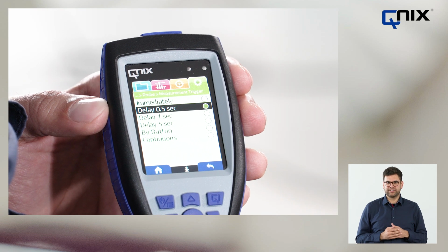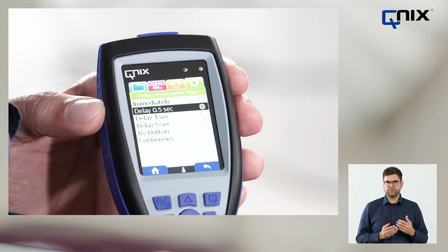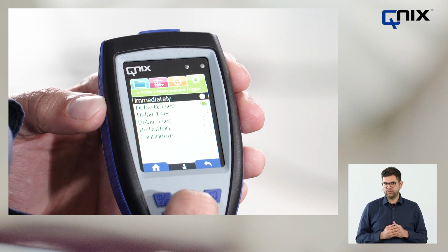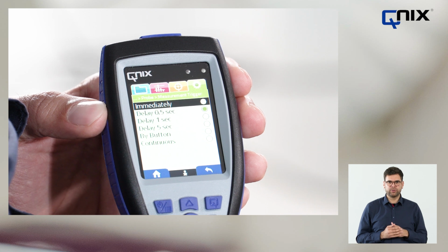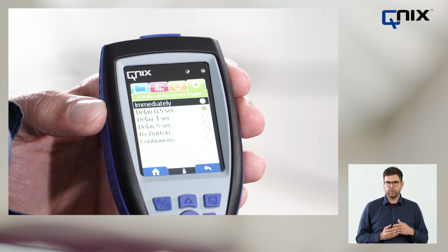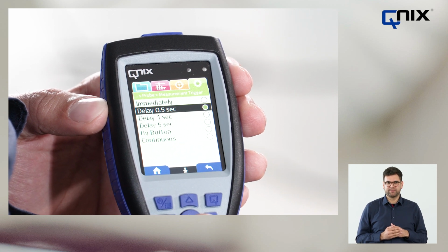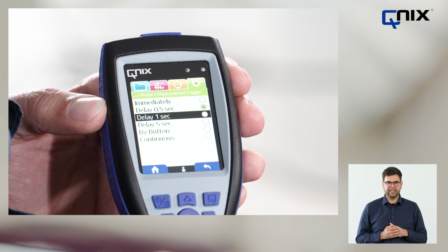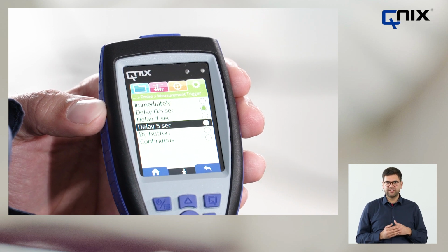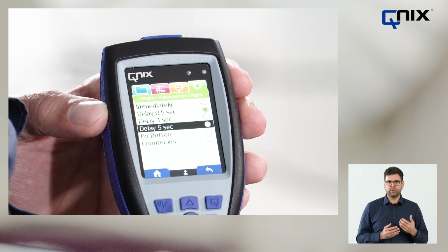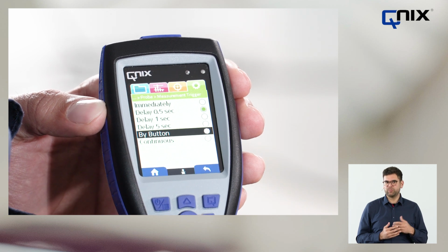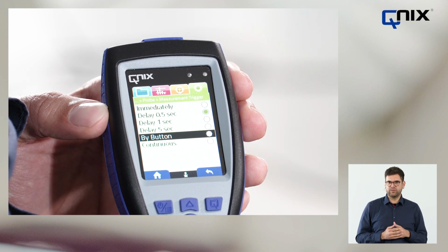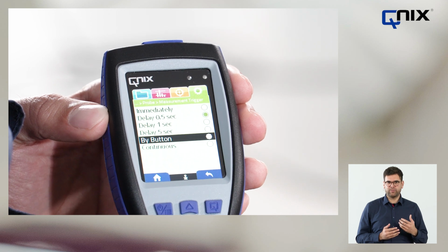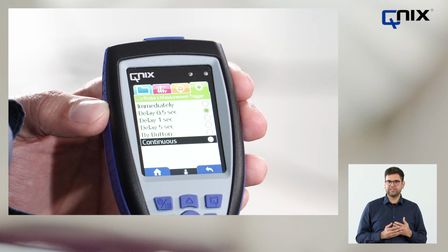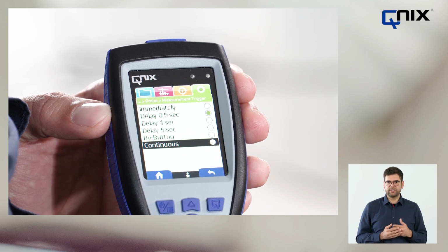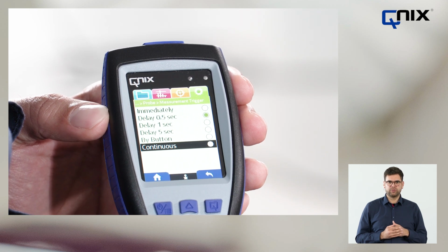This option offers the possibility of defining the recording of the measured values. By default, the probe records the measured values immediately when the probe is placed on a surface. Alternatively, we can delay the recording of the measured values. This has the advantage that when the probe is placed, the measurement becomes more stable. In addition, the device offers the option of recording the measurement only when the soft key is pressed, as an alternative to the options mentioned above.